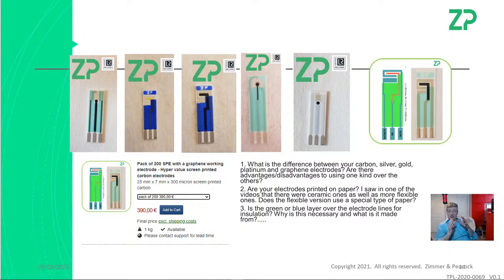We want to very much define the working electrode. In electrochemistry, the signal is often proportional to electrode area. So we define it by putting insulator everywhere and only exposing one part of the track, which we refer to as the working electrode. Otherwise, somebody could put their sample on there, and depending on how it spreads across the screen printed electrode, it could cover more or less electrode.